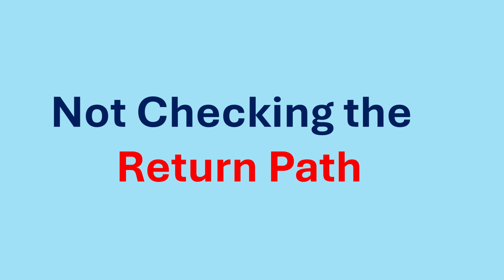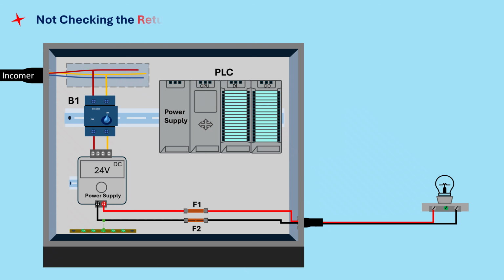Mistake number 4. Not checking the return path. Technicians often check the hot wire, but forget the return path. A broken neutral, or DC negative, can make a circuit look energized, but completely non-functional. Make sure the power has a way out and a way back. In most circuits, that means checking line and neutral, not line and ground. Checking line to ground is only for fault testing, not normal circuit verification.